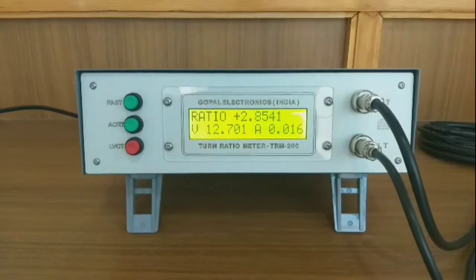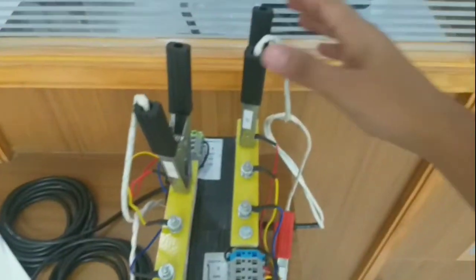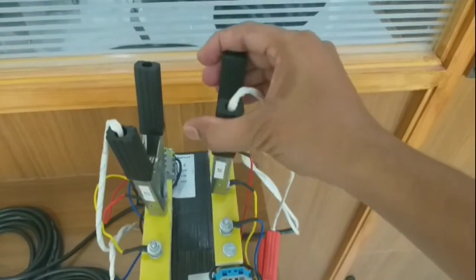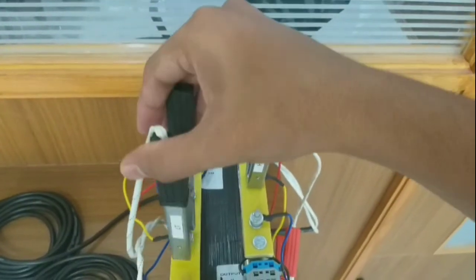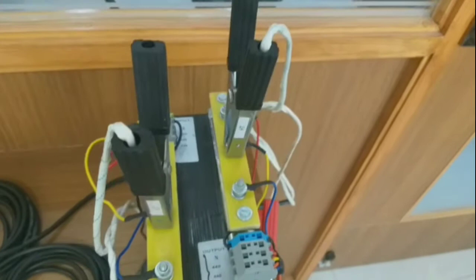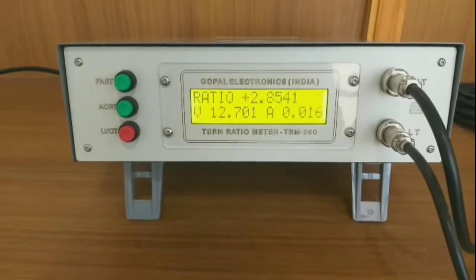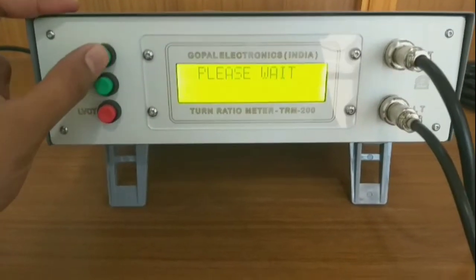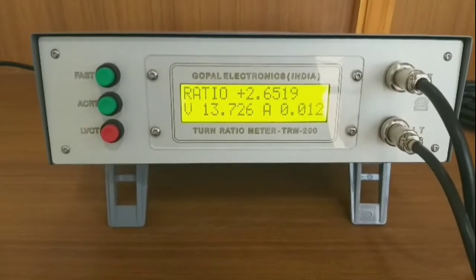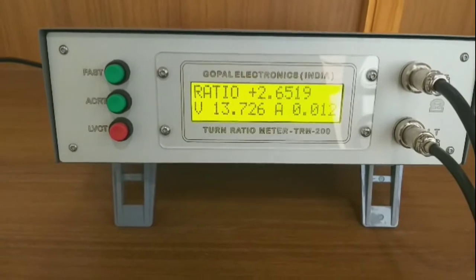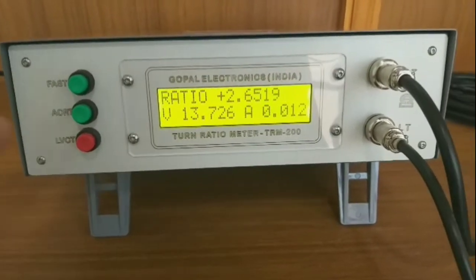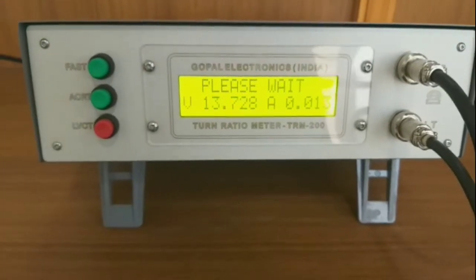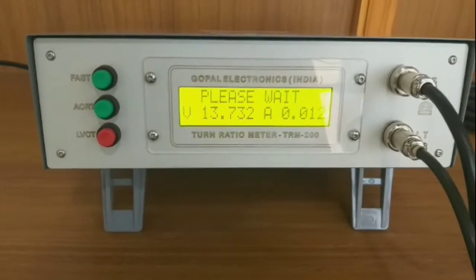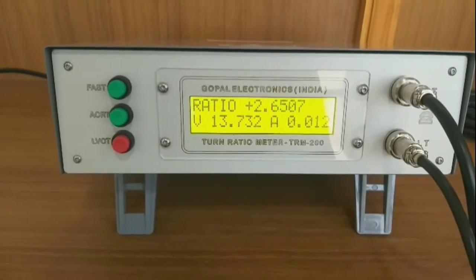In the same way, we will measure the turn ratio of Y phase. For that, change this lead from R terminal to Y terminal. We will see fast mode. Press the fast button. Now it is showing the turn ratio of Y phase in fast mode. In the same way, in accurate mode, it applies all mathematical filters and gives the result. Press the accurate button. Now it is showing the turn ratio of Y phase in accurate mode.